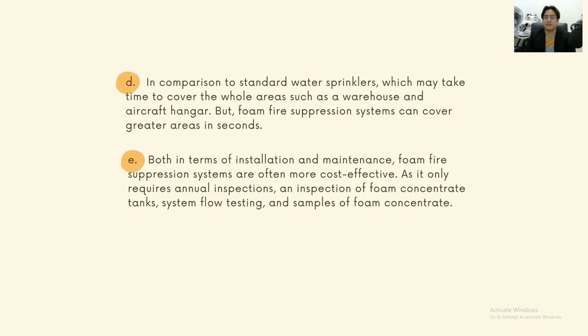Both in terms of installation and maintenance, foam fire suppression systems are often more cost effective as they only require annual inspection and inspection of foam concentrate tanks, system flow testing, and sampling of foam concentrate.